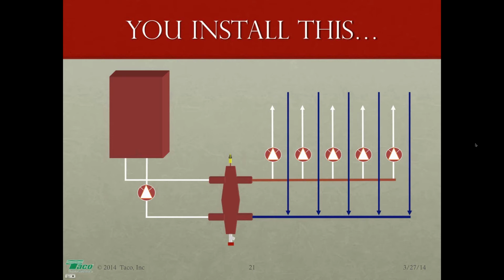Now, I want to get to a couple questions before we jump into buffer tanks. Ryan asks, wouldn't you supply the lower temp branches last after the high temp supply and then return them first? Again, if it is a cast iron boiler where the primary loop is in fact a loop that starts at the boiler outlet and goes all the way to the return, yeah, then you would have the hottest ones first, and then the lowest ones, and as they cascade down, the lower temperature outlets would be later on. In this type of an application with mixing, I may be wrong, but it doesn't appear to me that it would matter a whole heck of a lot. It's probably better to keep it simple and logical and straightforward. But in the big picture, I'm not sure it matters much because our cold return water is not being returned into the supply water that's going to the next supply.